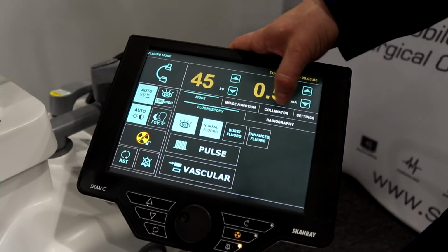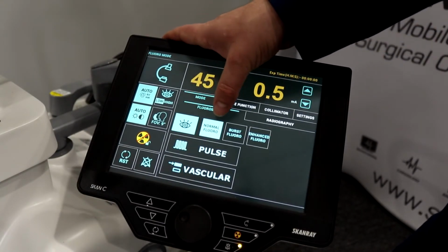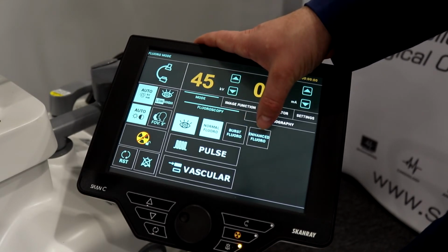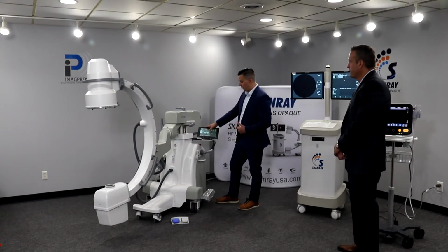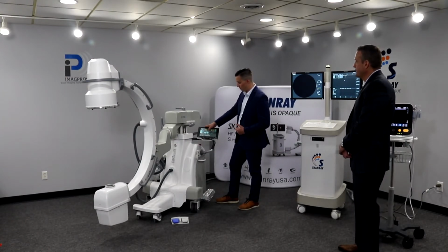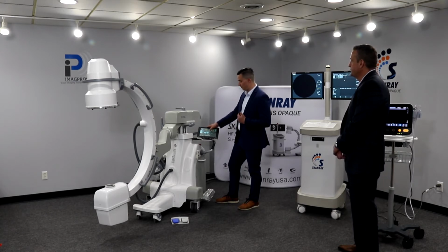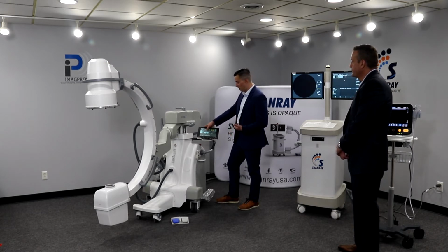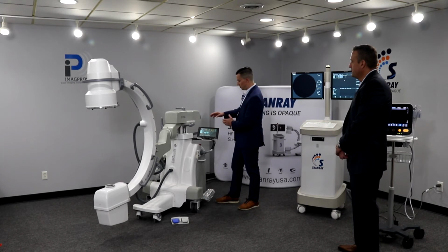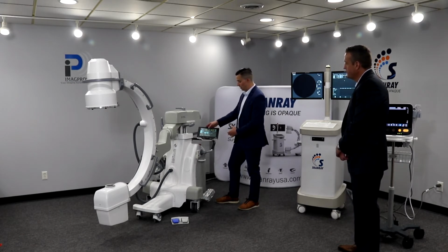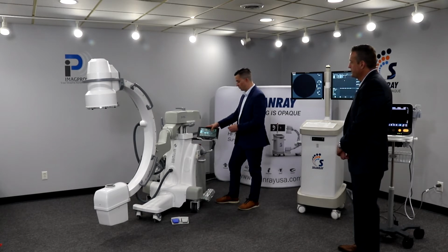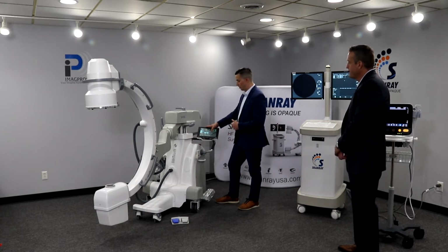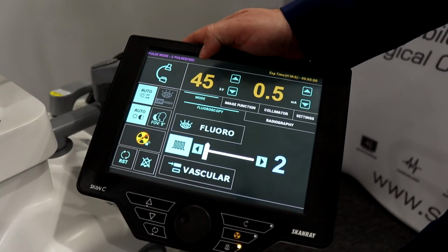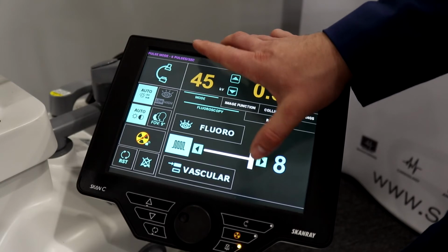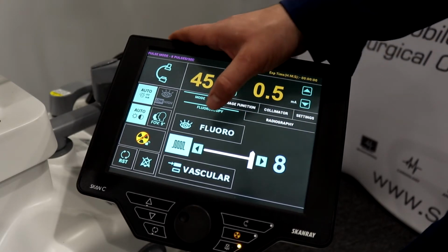The first one is called mode, and here we can access 3 different fluoro modes. Our system is able to take exposures at 30 frames per second, and we have 2 other modes, normal and enhanced, that can divide the frames per second to increase image quality without necessarily increasing dose. You can use these options to not change the dose delivered to the patient, using a software algorithm to merge frames 2 to 1 or 3 to 1 to deliver better image quality. We also have pulse mode in 2, 4, 6, and 8, and here you can optimize the lowest dose of the system possible.